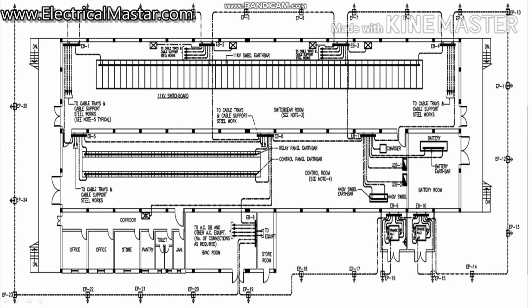From earth pit number 15, one connection goes to earth bus bar number 10. From earth bus bar 10, they take the earthing of the transformer body, and the neutral transformer grounding is taken separately. It is connected separately to earth pit 15. See here transformer number 2, it is the same way with EP16. One end is directly connected to earth bus bar 9.